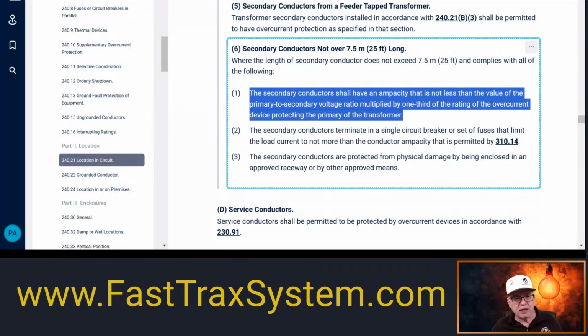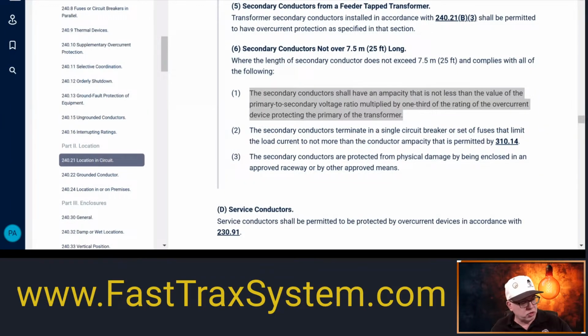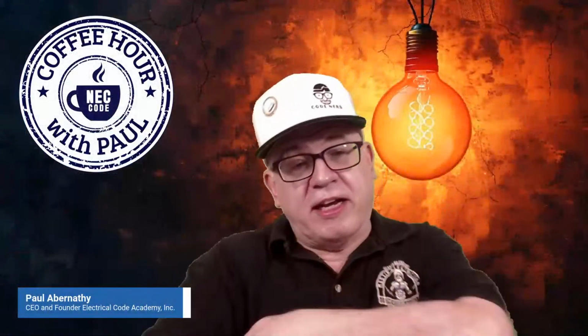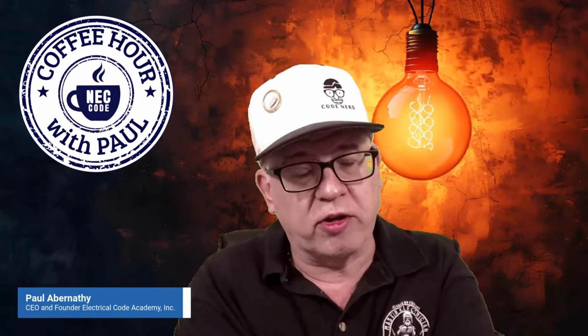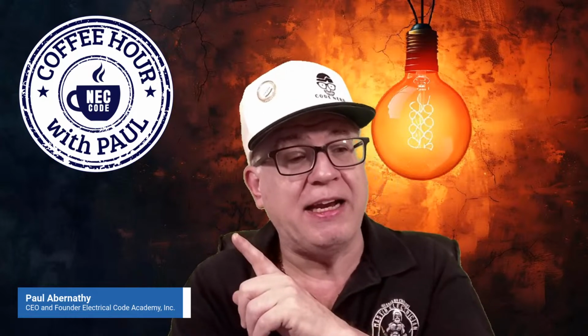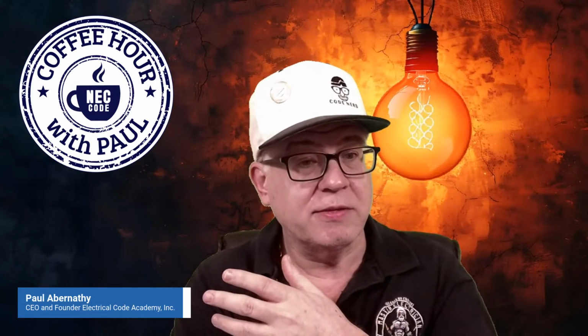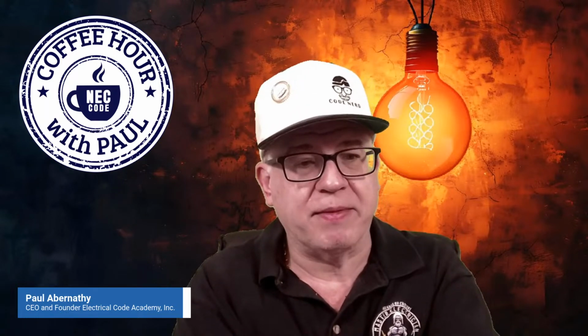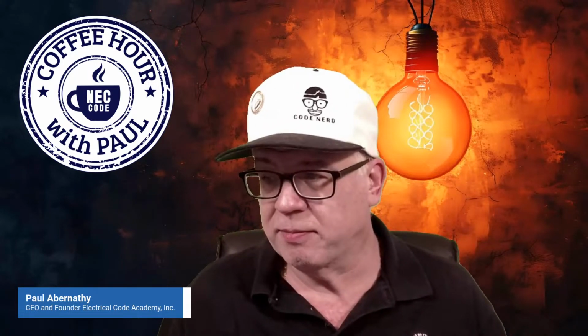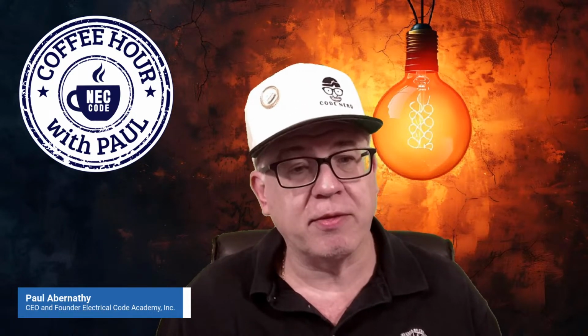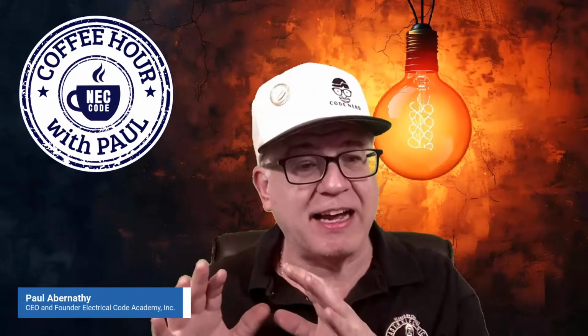I also remember that there's nothing in the code that says I could not put a 300 amp panel on the secondary side of that transformer. The panel might be oversized, and you're going to overload and overdrive and shorten the lifespan of your transformer, right? But nothing says that I can't do that in the code. It doesn't limit me. But the moment that I do that, then the conductors have to be sized for the overcurrent device that they're connecting into, right? But as far as a minimum size rule, we have to make sure that our conductors are at least sized based on the calculation. They're at least that size of conductor.